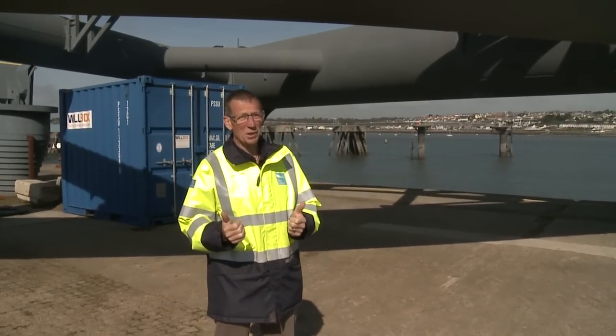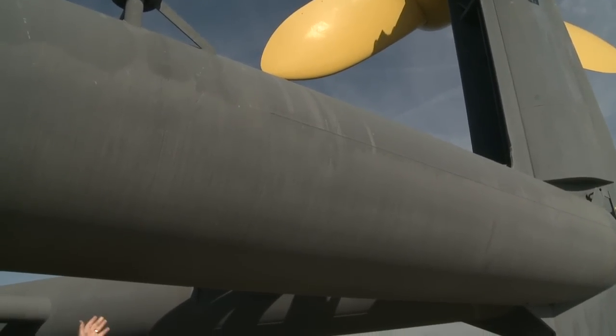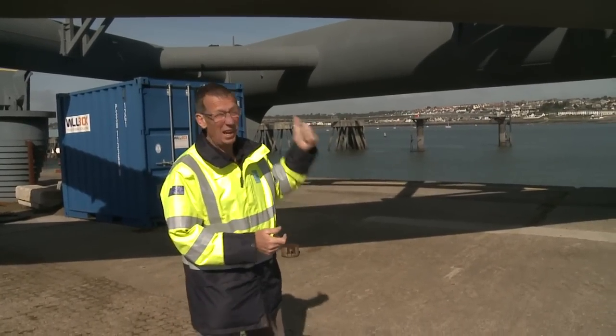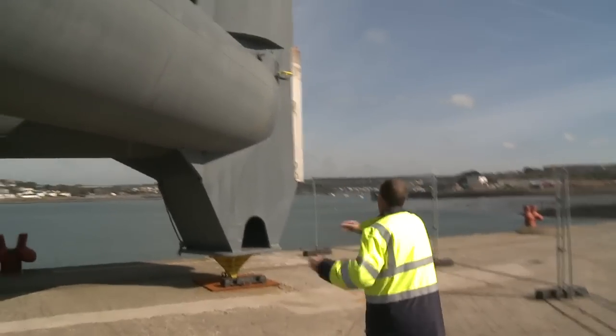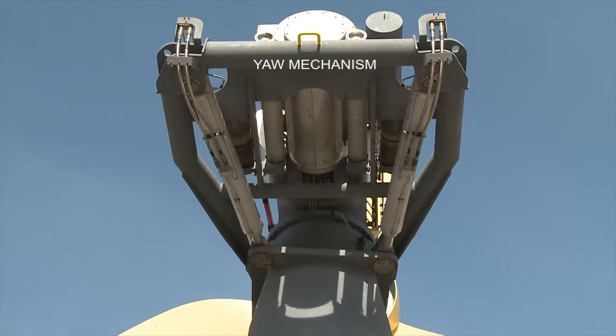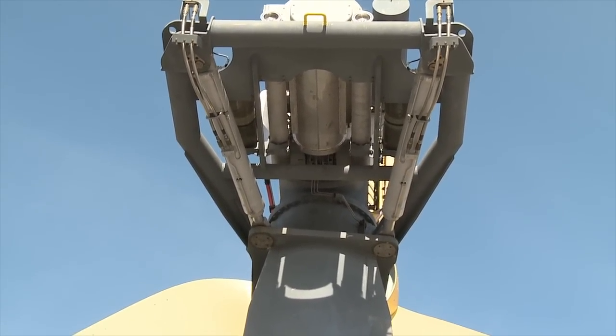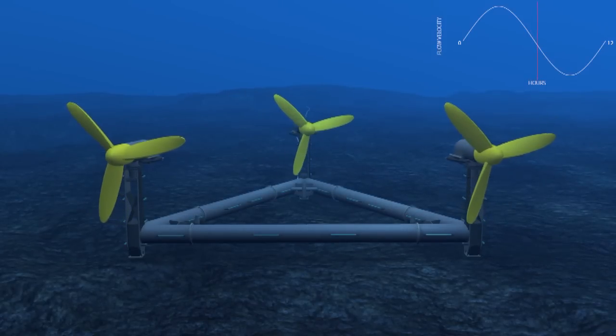Our base frame is a lightweight structure. The port tube above is 16 metres long, 2.2 metres in diameter, and made of 20mm thick steel. The rest of the frame is made up of three nodes — two at the front end and one at the rear. The nacelle itself is mounted on a large pinion bearing. Directly underneath the drive train is the yaw mechanism, featuring two very large hydraulic rams that drive the nacelle into the ebb and flow current. The nacelle can yaw up to 100 degrees in either direction from its starting position.